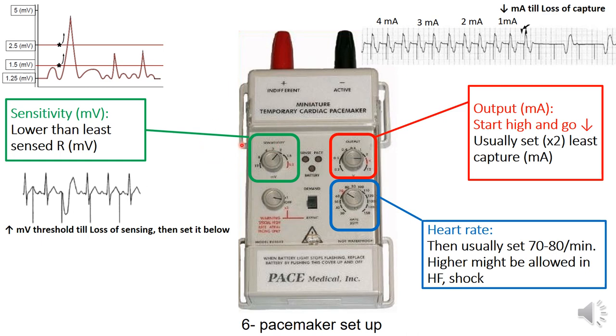The third parameter to set is sensitivity — in simple terms, the threshold at which the pacemaker detects the patient's native heart rhythm. If we set sensitivity too low, the pacemaker may sense the T wave and become inhibited inappropriately. On the other hand, if sensitivity is set too high — above the QRS voltage — the pacemaker may not detect the native heart rate and fire continuously in an asynchronous mode.